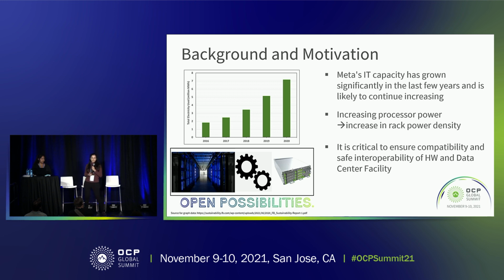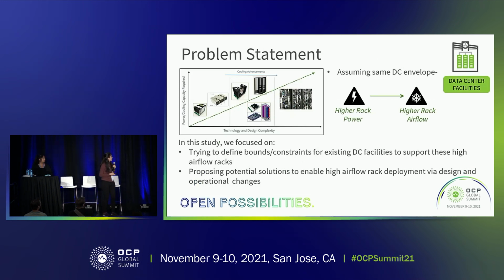With these higher power racks, it becomes really critical to evaluate what kind of cooling availability we have in our data centers and how we are able to ensure that we can support all these racks in our fleet. Also, safe interoperability between the data center and the IT equipment that we are deploying becomes critical. If you look at the graph here, you can see that the power and cooling capacity required has gone on increasing, just as the technology and design complexity has gone on increasing. And if we are assuming the same data center envelope, which means that we are supplying airflow at the same temperature, and all other infrastructure and constraints remain the same, then higher rack power directly translates to higher rack airflow requirement. Which brings us to our problem statement, really.